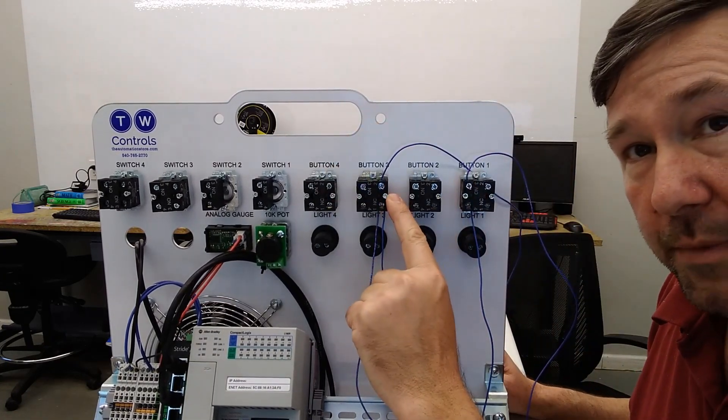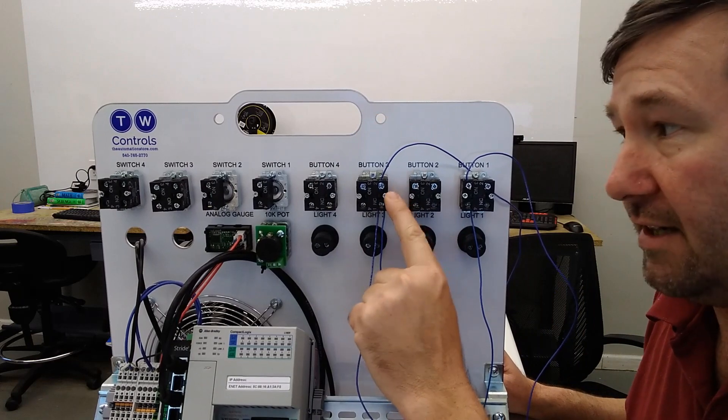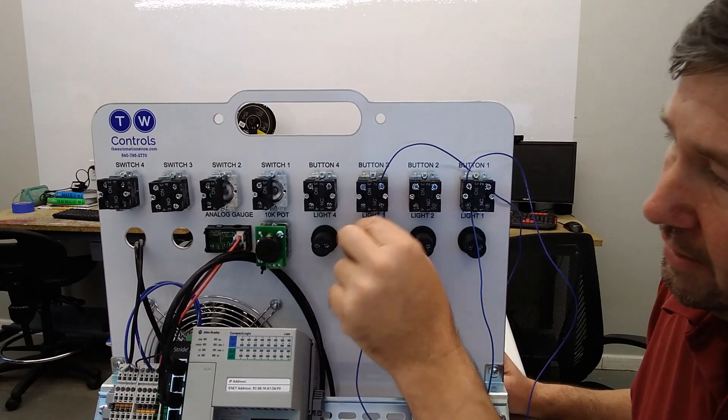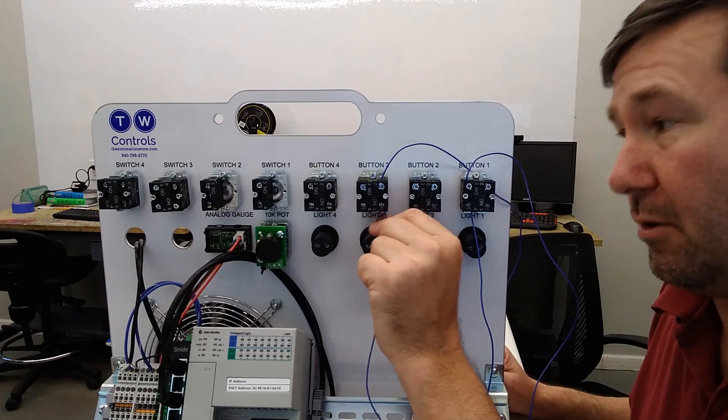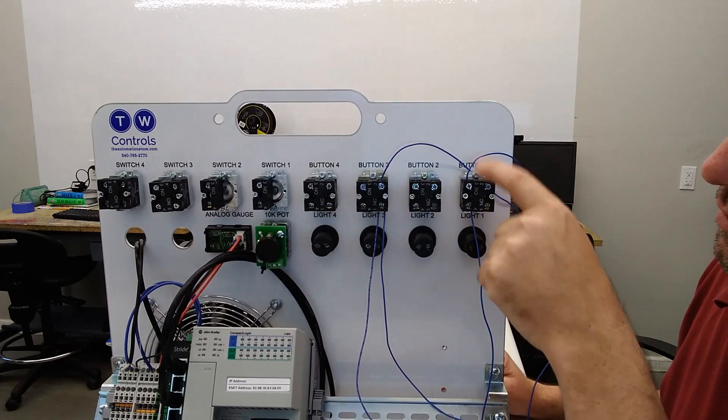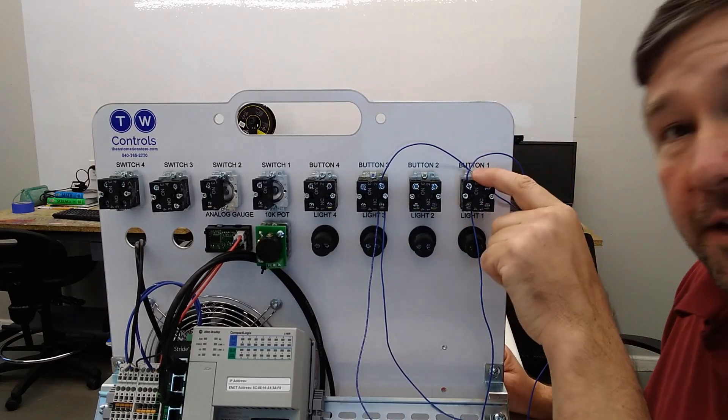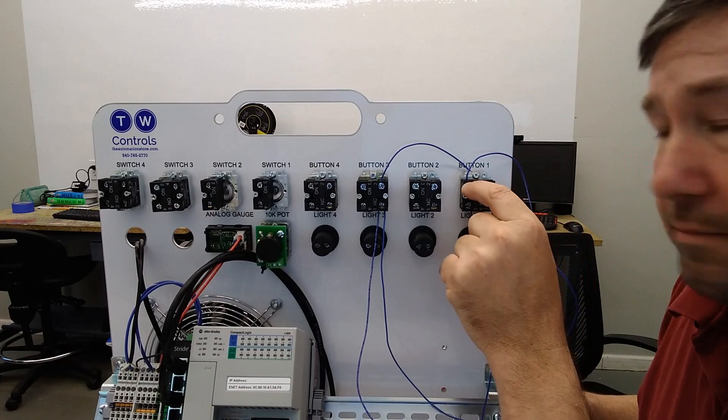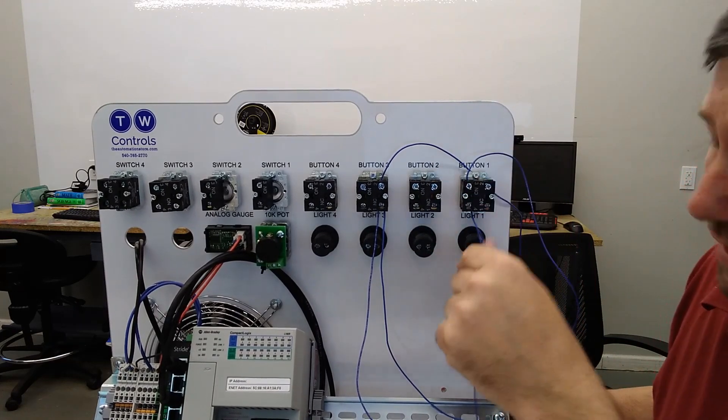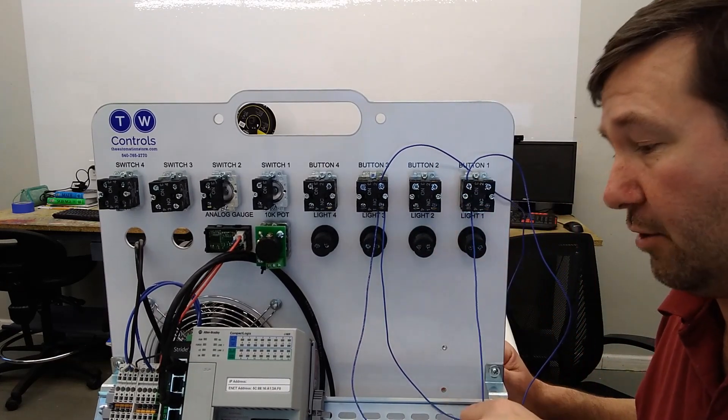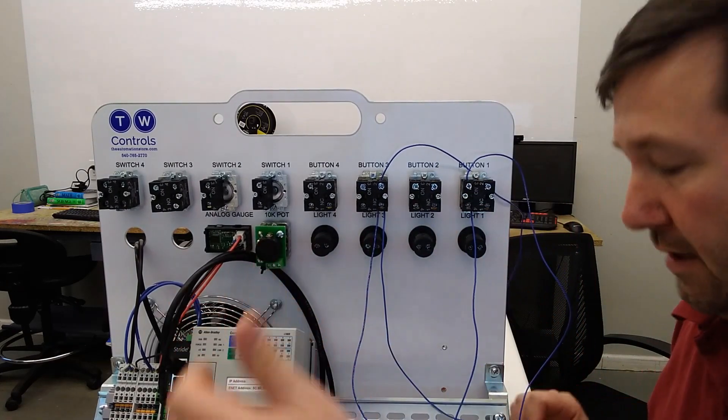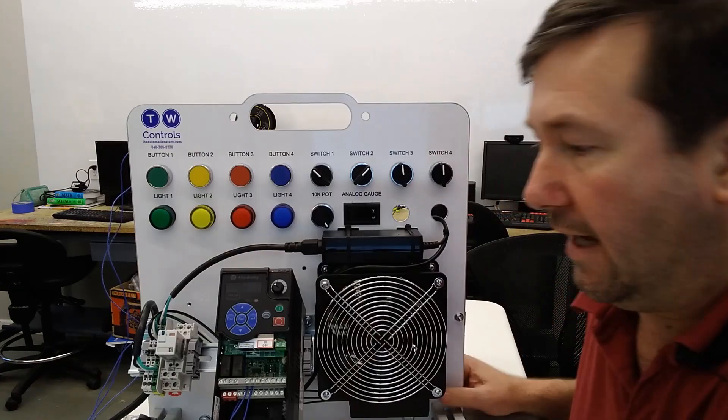So terminal 11 to the top of our normally closed contact on our red button 3. Out of the bottom of it, we're going to connect to terminal number 1 and jumper over to the top of our normally open on our green button 3. And out of the bottom of it, it's going to go back to terminal number 2. And that is it.